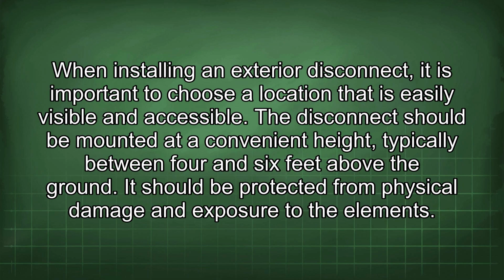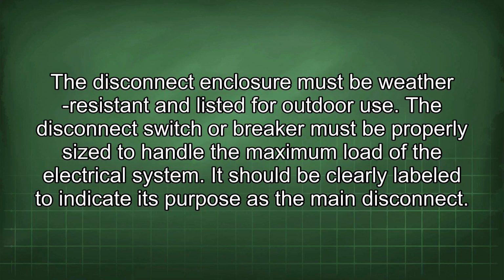When installing an exterior disconnect, it is important to choose a location that is easily visible and accessible. The disconnect should be mounted at a convenient height, typically between 4 and 6 feet above the ground. It should be protected from physical damage and exposure to the elements. The disconnect enclosure must be weather resistant and listed for outdoor use. The disconnect switch or breaker must be properly sized to handle the maximum load of the electrical system. It should be clearly labeled to indicate its purpose as the main disconnect.